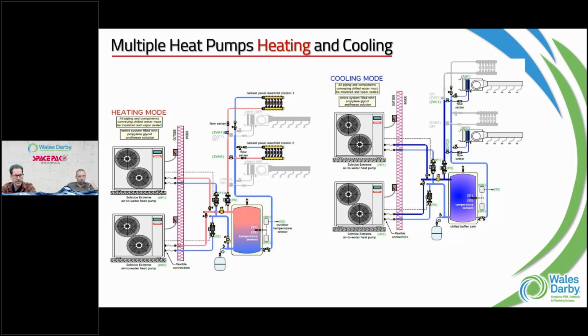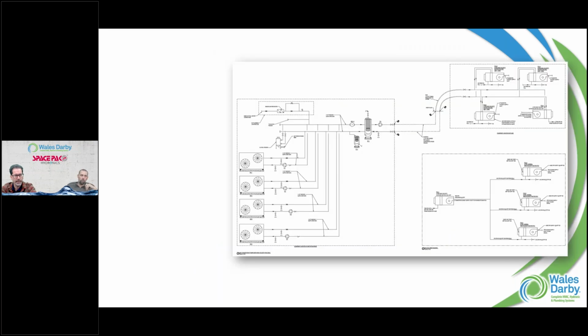And I know you said it earlier, but just be aware, if you're not that refrigerant-savvy kind of company, water's been your medium. These are sealed units in that respect, so you're really just resorting back to what you've been doing, and that's okay. Know what my loads are, what this produces. I'm doing pumping and piping, sizing circulators, sizing my delivery of what size PEX or pipe, copper rather, or even brass.